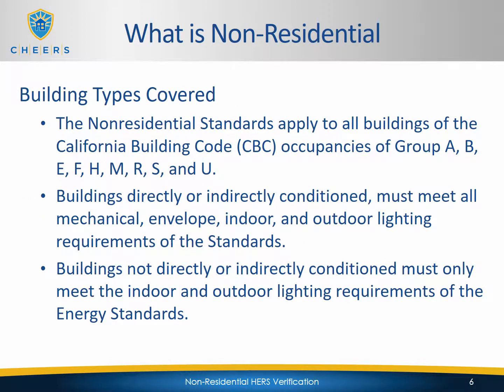What is considered non-residential? The California Building Code has different building types considered different occupancy groups, lettered as groups A, B, E, F, H, M, R, S, and U. For buildings that are directly or indirectly conditioned, they must meet all the mechanical, envelope, indoor and outdoor lighting requirements of those standards. Buildings that are not directly or indirectly conditioned only need to meet the indoor and outdoor lighting requirements.